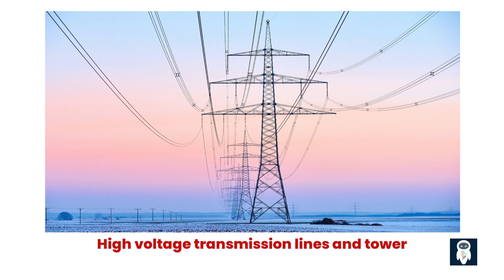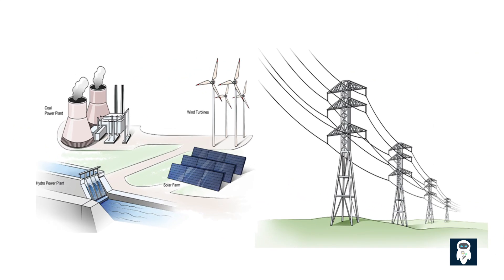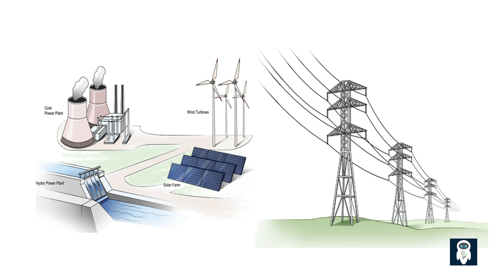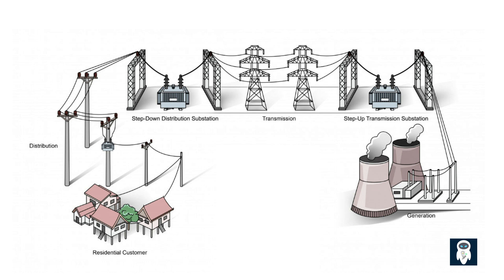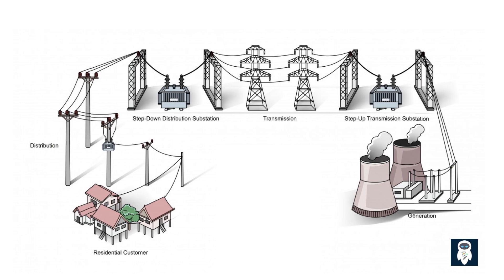You might be wondering why there are two power lines on each pole for high-voltage transmission lines. The primary reason is redundancy and increased capacity. By having two power lines, the system ensures redundancy in case one line fails or needs maintenance. It allows for uninterrupted power supply even if one line is out of service. Imagine the impact if an entire region lost power due to a single line failure. Moreover, having two lines doubles the capacity of the transmission system, allowing for a higher amount of electricity to be transmitted, meeting the increasing demands of industries and households.